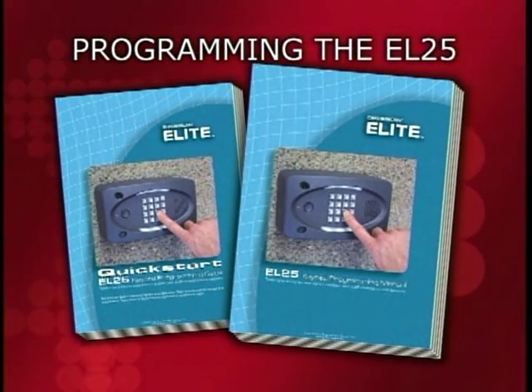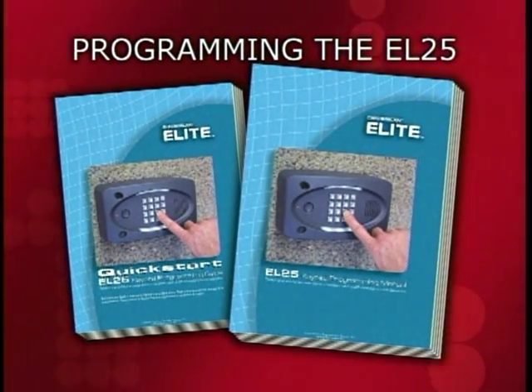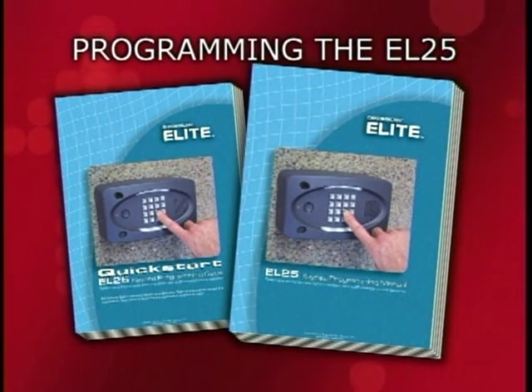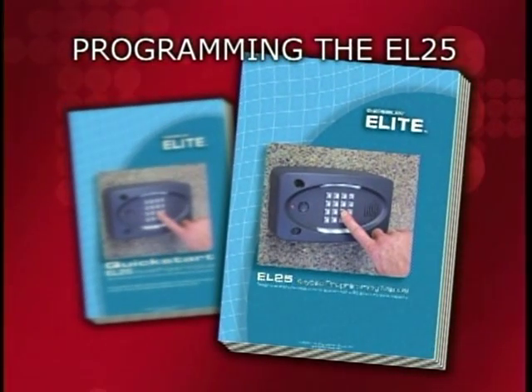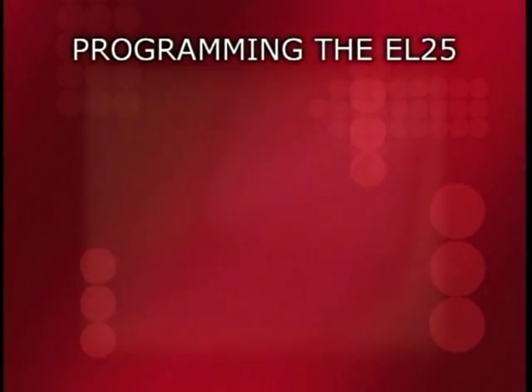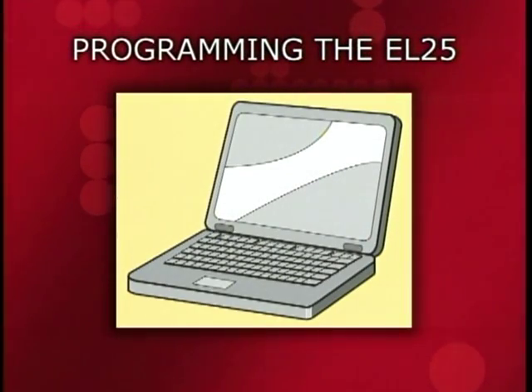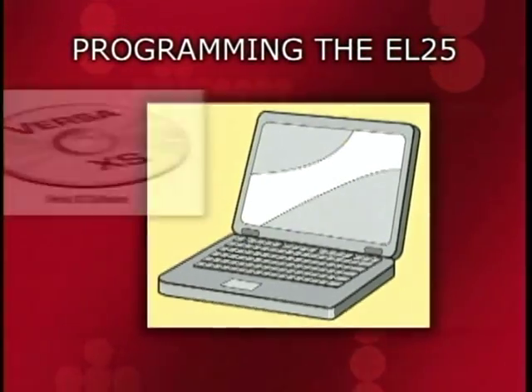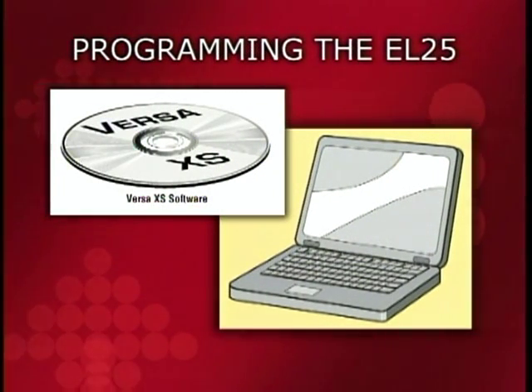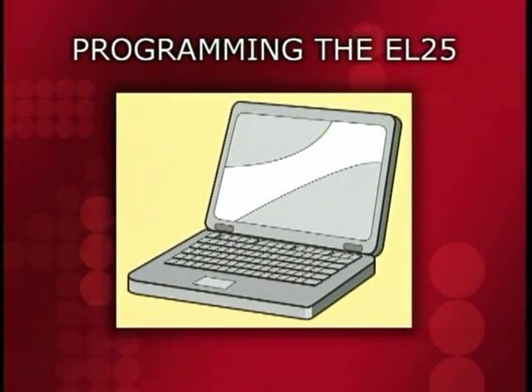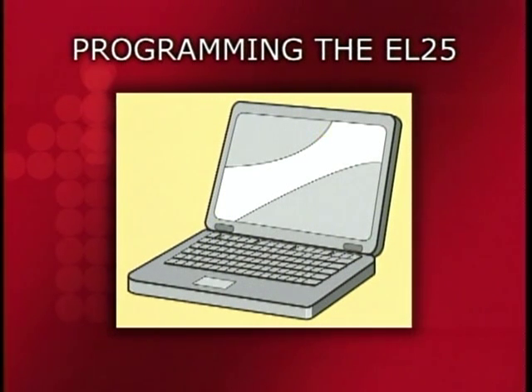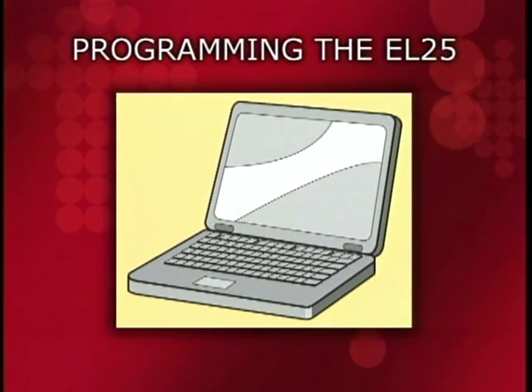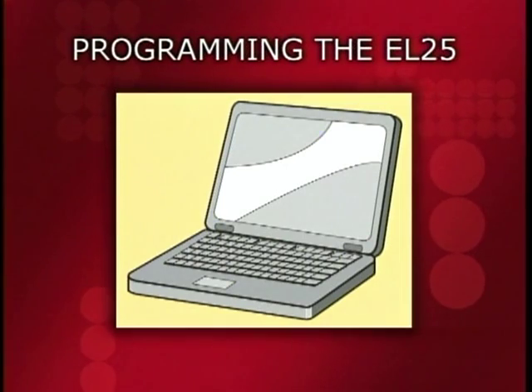Programming the EL25 can also be performed using your computer and the Versa XS software provided with the unit. Connections to the unit can be made either by direct connect cable or by dialing into the unit's modem when it is connected to a telco line. The direct connect cable attaches to the serial port of your computer into the J301 connection inside the EL25. See the advanced programming guide provided with the unit for programming instructions.